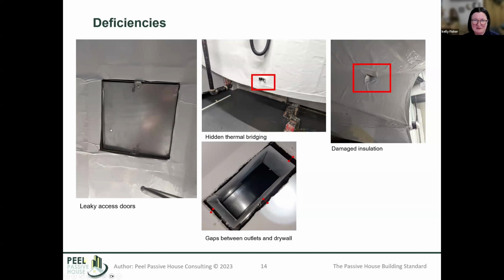In larger systems, you're likely also going to have access doors and access panels. So making sure that these don't offer any additional leakage that really hurts you along the way. And then just being mindful as well, I always like to throw in some other examples of hidden thermal bridging in the duct insulation, or damaged insulation for low clearances. These don't really impact your pressure loss or your leaky ductwork, but really impact some other things along the way.